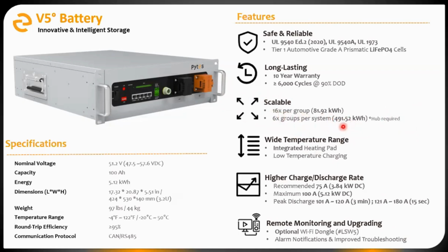That's going to give you close to 492 kilowatt hours. There is a special accessory required, called the hub, to build a system that large, and I'll show that a bit later. But really, from a single battery, which is 100 amp hours, 5 kilowatt hours a piece, all the way up to 96 total batteries, just under 500 total kilowatt hours, this is a very scalable solution that works for an extremely wide range of applications and system sizes.